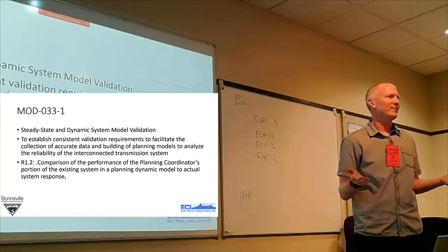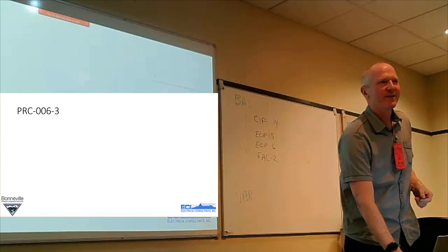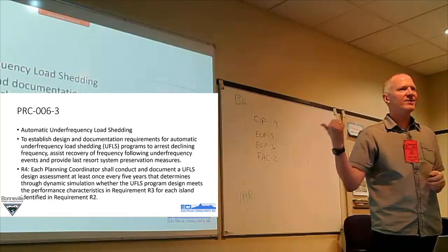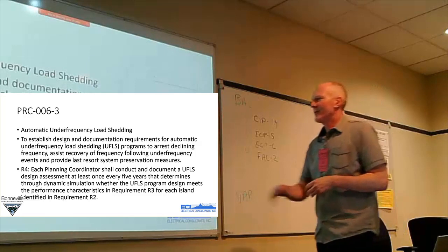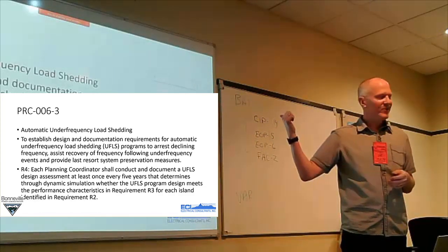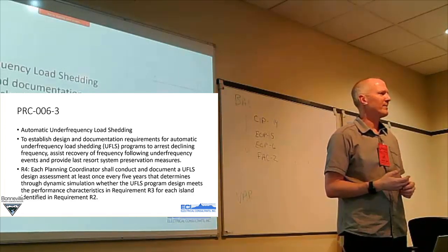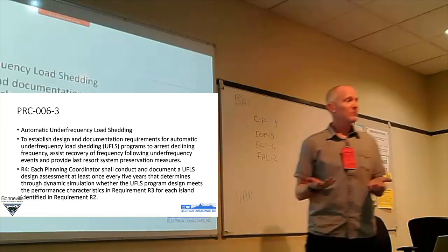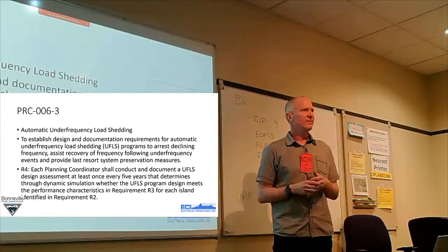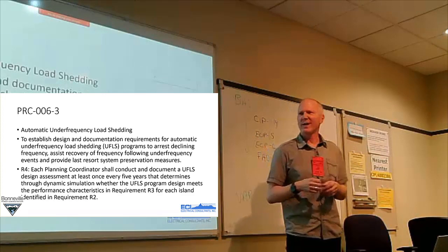Okay, what's after MOD-033? We'll just roll through a couple. Any guesses? PRC something? What's PRC-006? You can use TS here, through dynamic simulation, right? How about that? Anyone ever done this? Anyone done underfrequency load shedding for Bonneville, right? We submit stuff. Isn't this the stuff we send to Northwest Power Pool? Yeah. Let them know what the thing does. And these are relays, right? If you look in PowerWorld, which we might play with some of these, it's one of the many models you can put in the tool, and you can define the underfrequency, undervoltage relay stuff in a generator, which we might get to tomorrow.